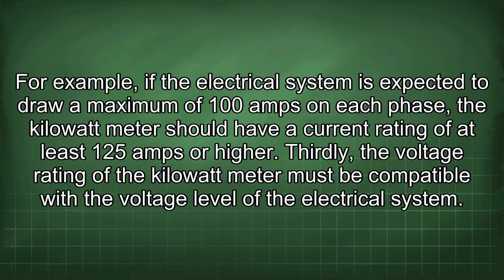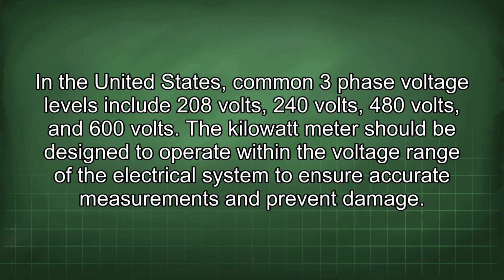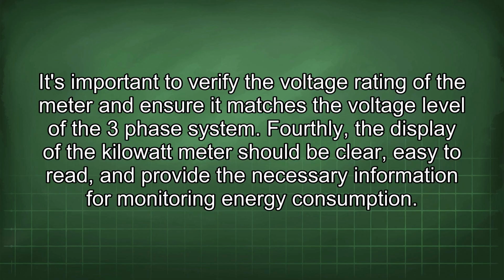Thirdly, the voltage rating of the kilowatt meter must be compatible with the voltage level of the electrical system. In the United States, common 3-phase voltage levels include 208 volts, 240 volts, 480 volts, and 600 volts. A kilowatt meter should be designed to operate within the voltage range of the electrical system to ensure accurate measurements and prevent damage. It's important to verify the voltage rating of the meter and ensure it matches the voltage level of the 3-phase system.